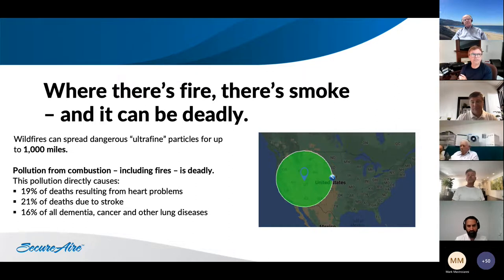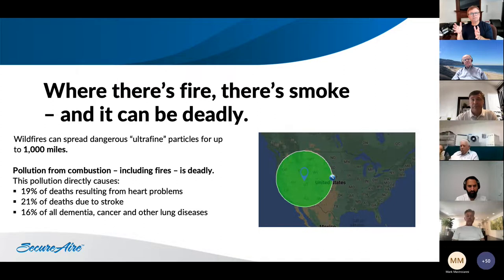It's interesting too, because yes, 100% outside air is really great from a standpoint of infection control, but obviously there are expenses on energy, as you just mentioned. As you showed, you've got 100% outside air coming in and smoke was getting in the building from wildfire smoke. So you had to retrofit and try to come up with a temporary carbon solution. That drove up energy expenditure too, because you had to pull across those carbon filters, that carbon media. It helped some.